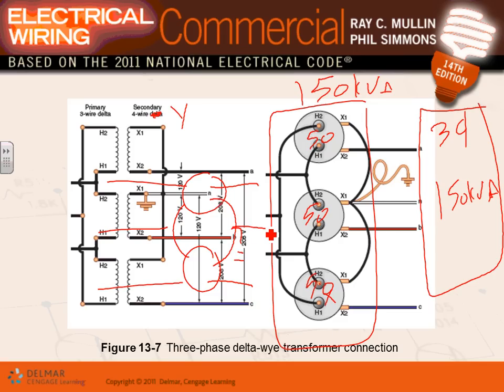So here you got yourself an open... I'm sorry, this is not the grounded part. Here's phase A, phase B, phase C, and in this case, where's my neutral? This is a Y. You have to rehook them, and if it has a component right here, guys, that would be where they ground this, and that will get you your neutral. It's called open delta. That's it. But typically they don't, so it only burns one coil instead of three coils.